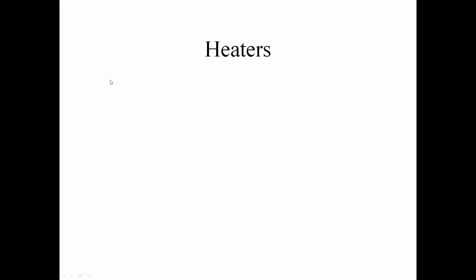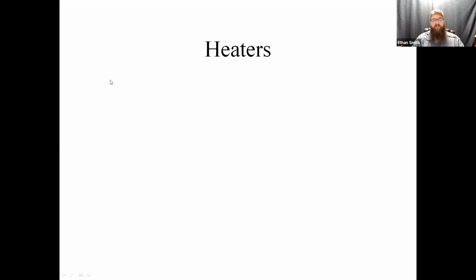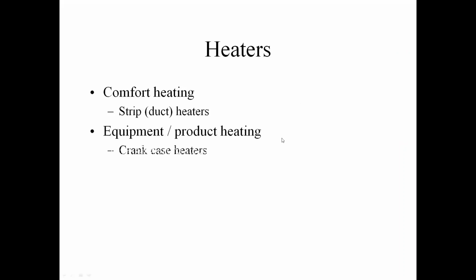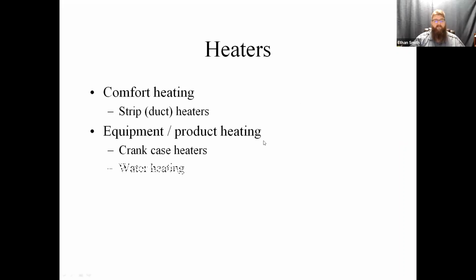Thermostats, kind of. Yeah, there is a heater in a conventional thermostat. The old analog thermostats had heaters in them. They were the heat anticipators. So they were that little piece of wire that went around the perimeter, had a little armature that you had to adjust. That was the heat anticipator. It was a little tiny piece of nichrome wire that was a heater. Where else might we see heaters, guys? We got that one already. Safety switches. Okay. Water heating, crankcase heaters. What about control panel heaters? Anybody ever encountered a control panel heater?